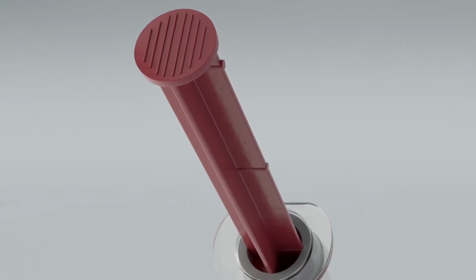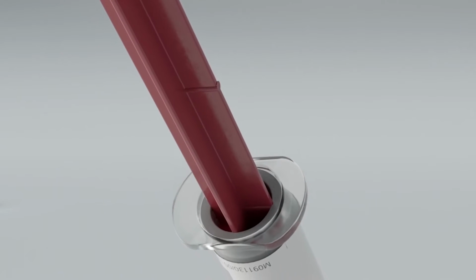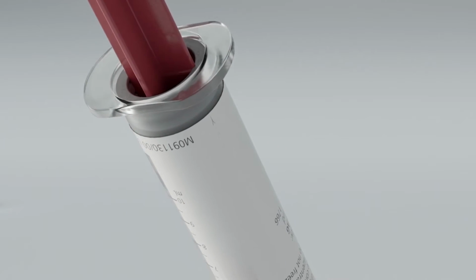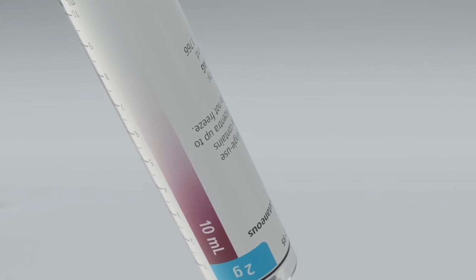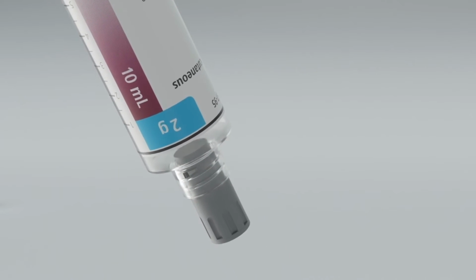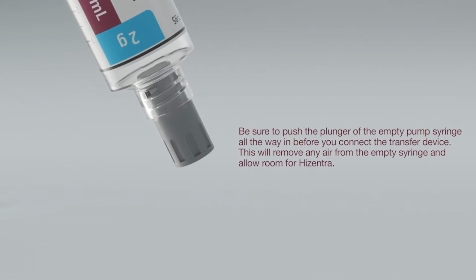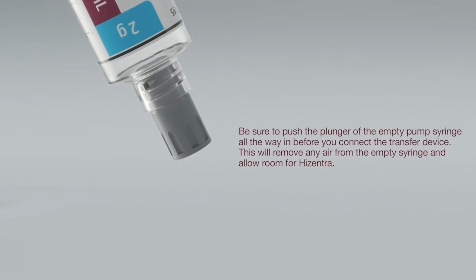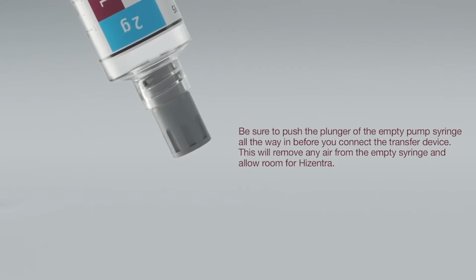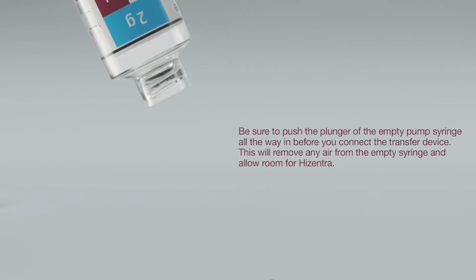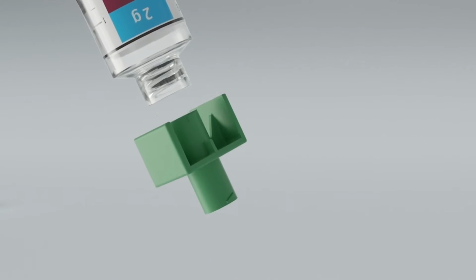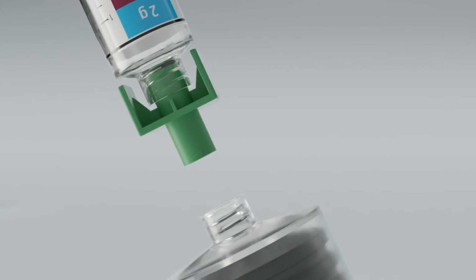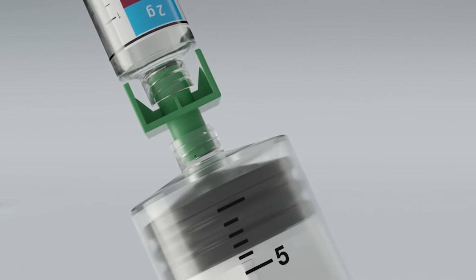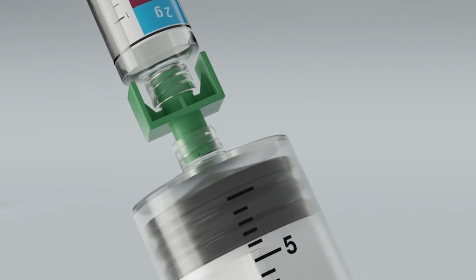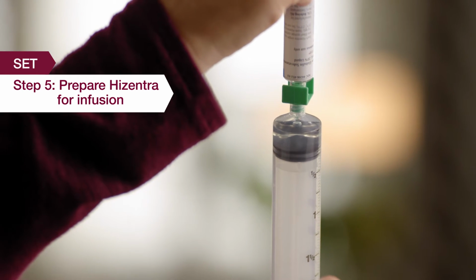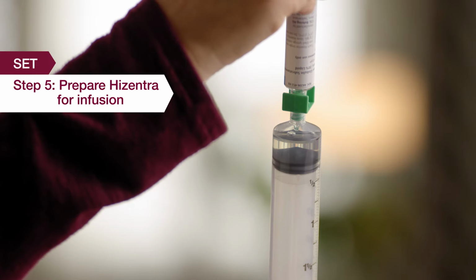If the Hizentra prefilled syringe does not match the infusion pump requirements, transfer the contents of the prefilled syringe to a syringe that is the size required by your infusion pump, using a syringe-to-syringe transfer device. Remove the protective cap from the prefilled syringe. Twist the transfer device onto the prefilled syringe. Then screw the empty syringe onto the other side of the transfer device. Push the plunger of the prefilled syringe to transfer Hizentra into the empty syringe.